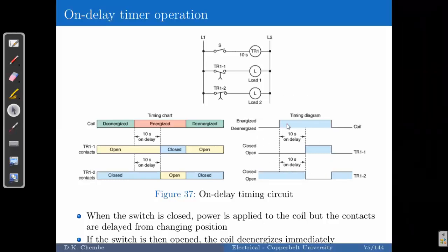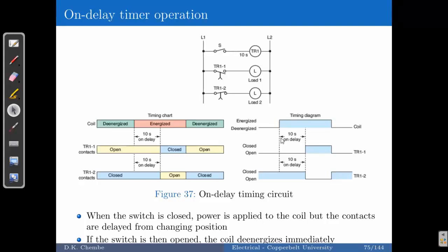These timing sequence graphs are easier to understand when read as timing diagrams. The top part represents energized and the lower part de-energized. When the switch is off the circuit is de-energized, and from the moment it is switched on the timing sequence begins — that is the delay time. One contact delays to close and the other delays to open. After 10 seconds one opens and the other closes, and they stay in that state until you switch off the switch.